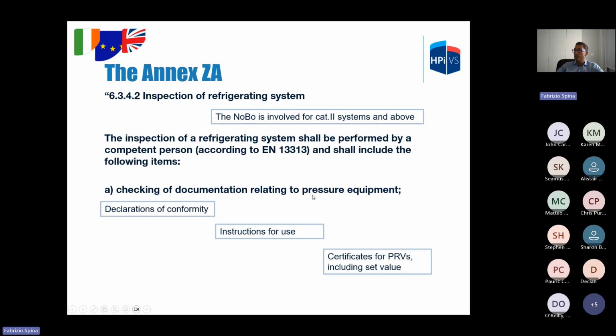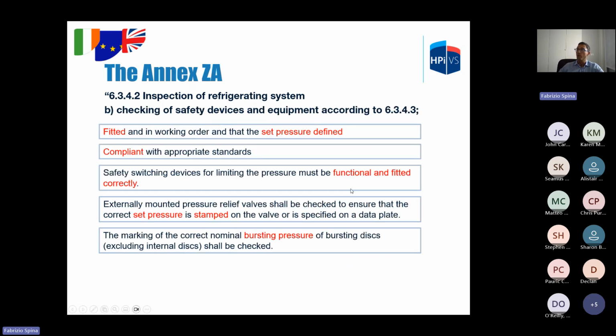Checking the documentation relating to pressure equipment, for example, declaration of conformity, instruction for use, or certificates for PRVs, including set value. Checking the safety device according to this point, and these are the points outlined. So fitted and set pressure must be clearly defined, compliant with appropriate standard and CE certified. Safety switching must be functionally fitted correctly. On pressure relief valves, the set pressure must be stamped on the valve or on a data plate. Same thing for the bursting pressure on bursting discs.